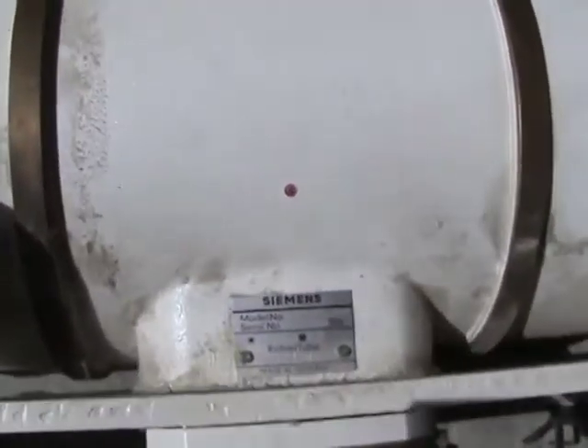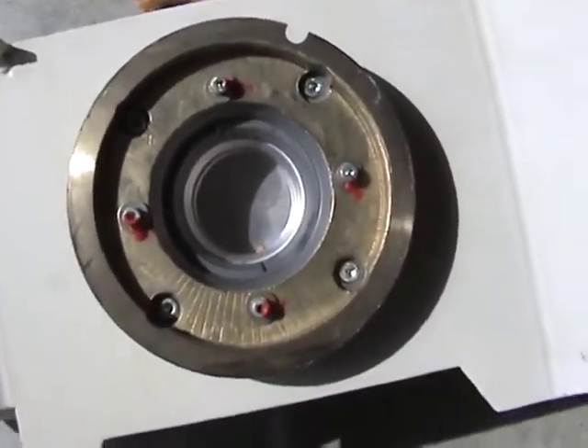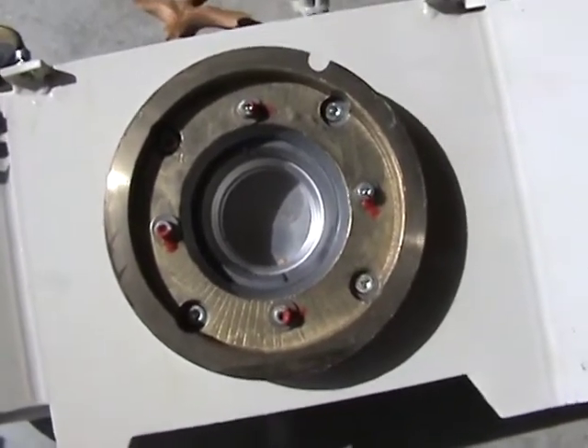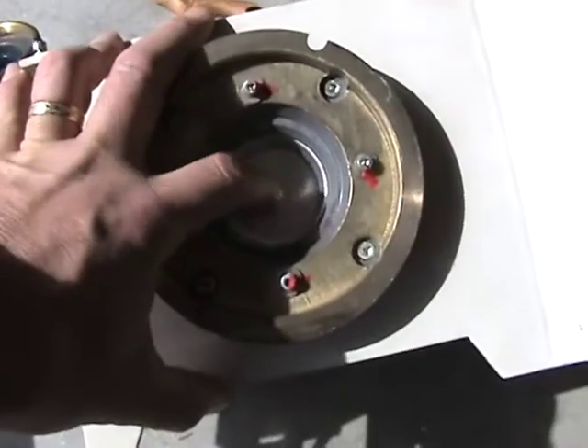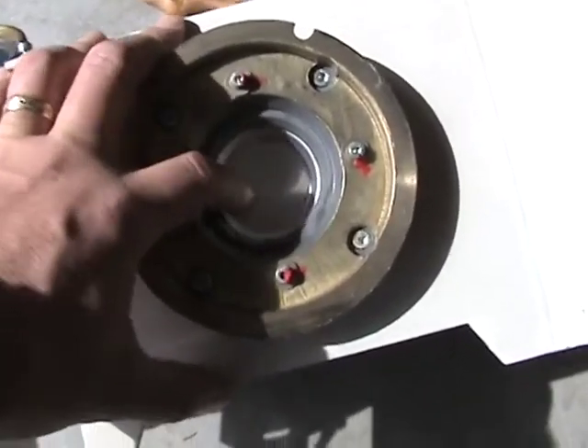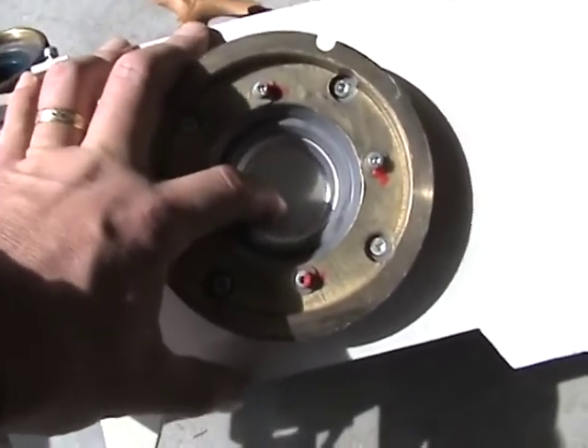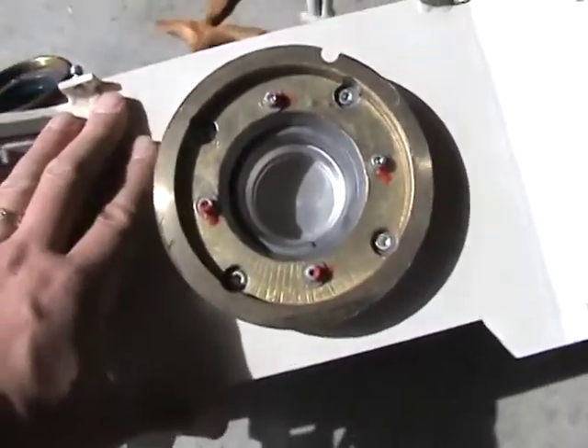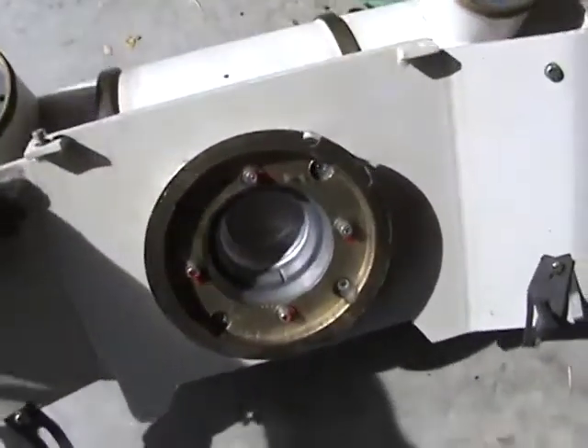Right there is the window - that's the window of the tube - and you'll notice that this window happens to be made of metal. I don't want to tap it too hard because it'd be bad if my finger went right through it. Beryllium is a very soft metal, also kind of expensive, but it makes really good windows for an X-ray tube.